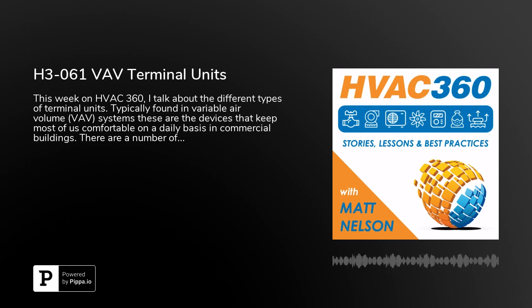Now, when you get into the variable volume boxes, VAV boxes, you have basically your single duct cooling only box, which is nothing more than a valve in a box. That's about as simple as you can get. You can also kick it up a notch if you want supplemental heating and cooling, and you can get it with a hot water coil and/or electric reheat coil. So those are some of the options that you can get with a single duct VAV box. Now you can get into more of a fan powered box.